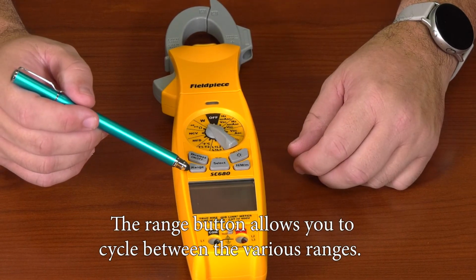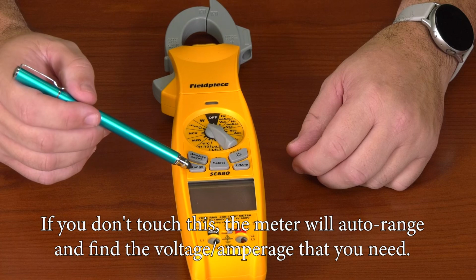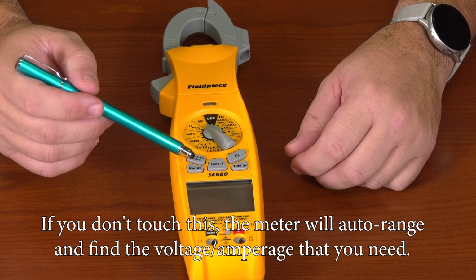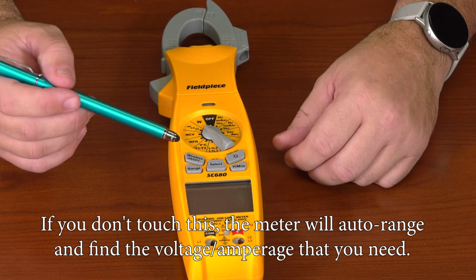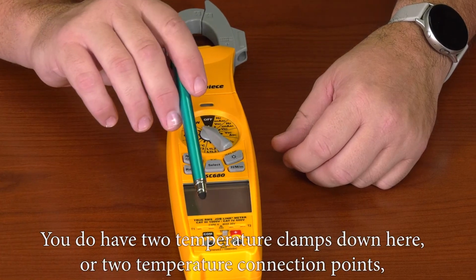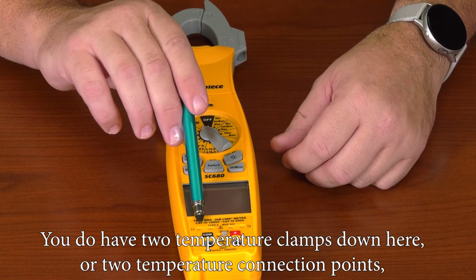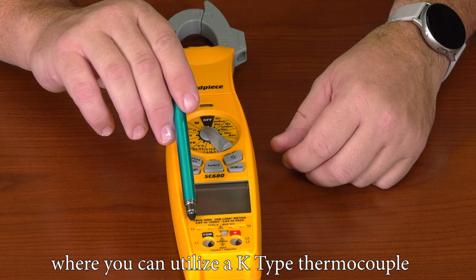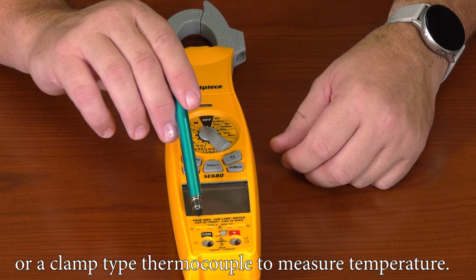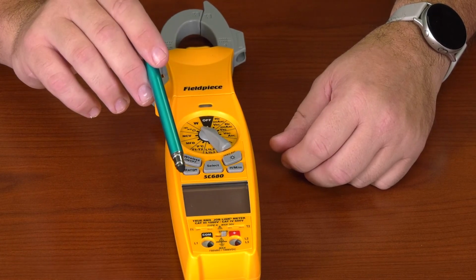The range button allows you to cycle between the various ranges. If you don't touch this, the meter will auto range and find the voltage or amperage that you need. You do have 2 temperature clamps down here, or 2 temperature connection points, where you can utilize a K-type thermocouple or a clamp-type thermocouple to measure temperature.